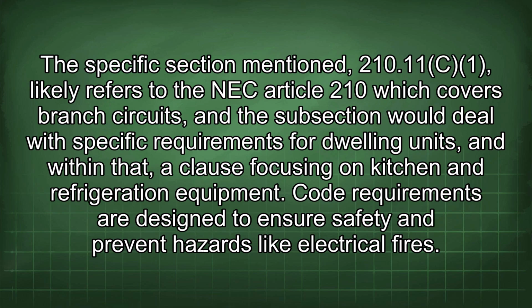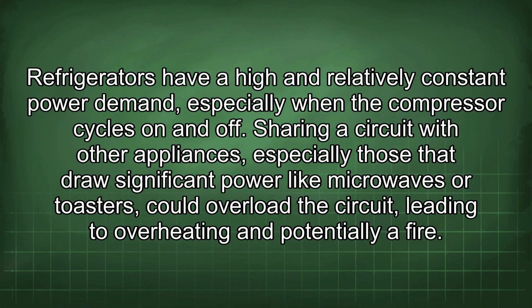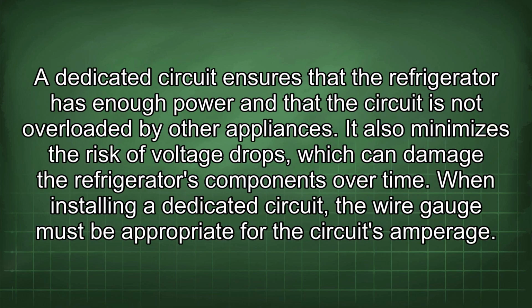Code requirements are designed to ensure safety and prevent hazards like electrical fires. Refrigerators have a high and relatively constant power demand, especially when the compressor cycles on and off. Sharing a circuit with other appliances, especially those that draw significant power like microwaves or toasters, could overload the circuit, leading to overheating and potentially a fire. A dedicated circuit ensures that the refrigerator has enough power and that the circuit is not overloaded by other appliances. It also minimizes the risk of voltage drops, which can damage the refrigerator's components over time.